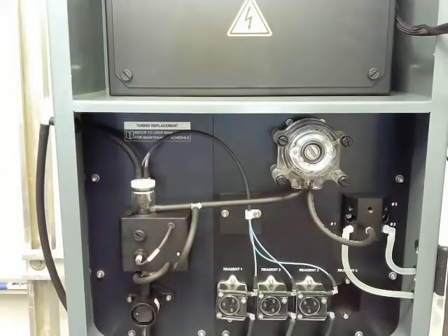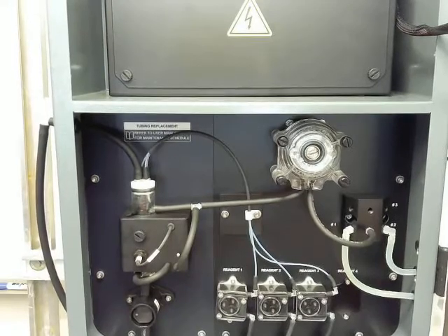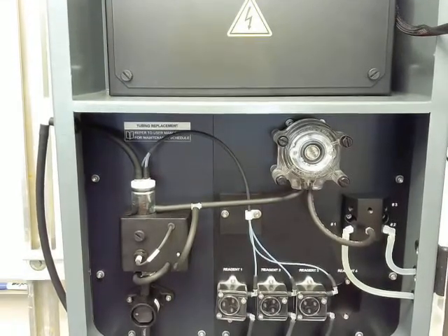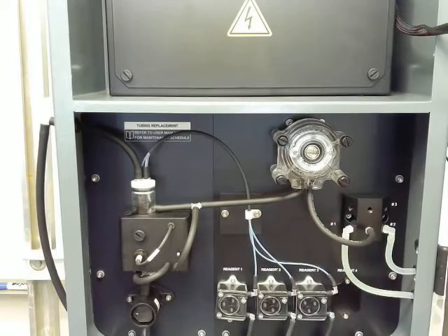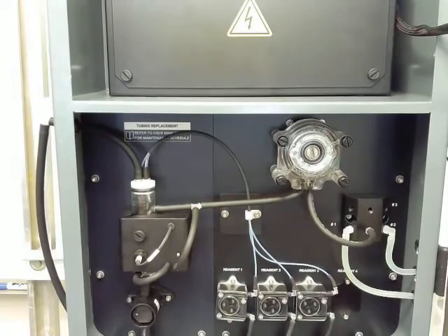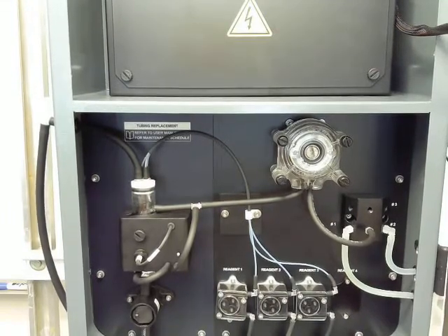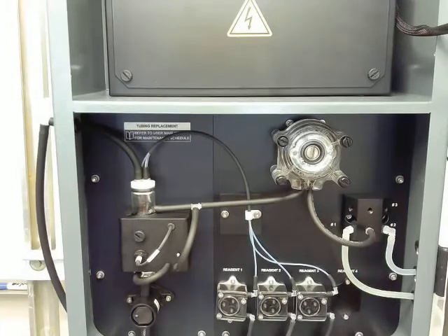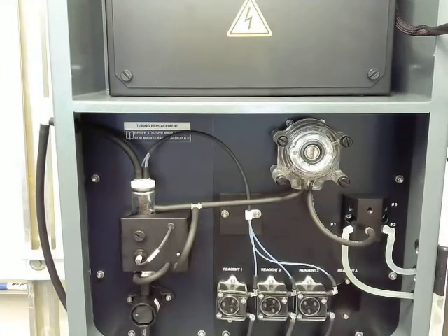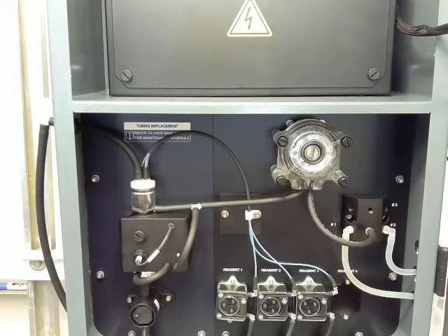We see our sample pump rotating now, drawing in sample. It's going to first rinse out the flow cell with whatever was in there from last time. This process is the same for an analysis cycle online or calibration. The only difference is that in calibration, our selection block has our calibration setting selected. Online, our selection block would have our sample selected. At the beginning, we do a rinse out. We see this flow cell fill up with sample 2 full times and then drain out.